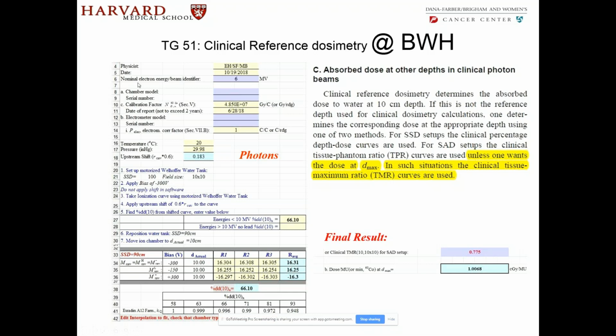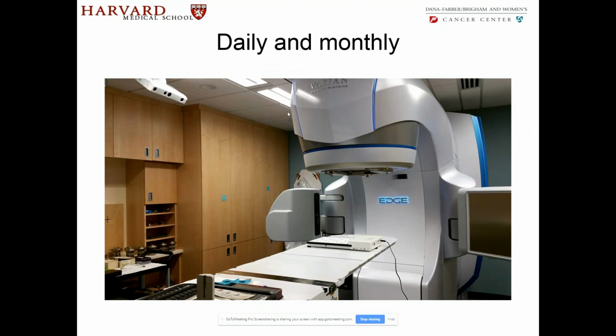This was done last month by three of us. It's usually good to have a second pair of eyes to check everything, even though one might have done this a few times. Okay, so that completes TG51. Now your machine is almost ready to use. What you need are daily and monthly checks. We have started using the Sun Nuclear device called the daily checker. You calibrate it and set it up for a daily check, and we have a monthly phantom as well that we use.